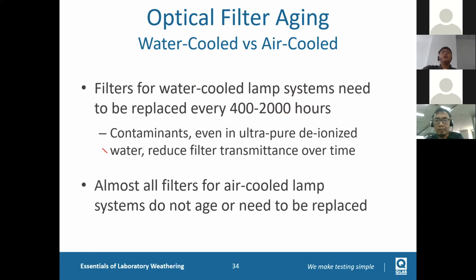Filters for water-cooled lamp systems need to be replaced every 400 hours for the inner filter and 2,000 hours for the outer filter. QLab does not manufacture any water-cooled system - QLab only has the air-cooled system.